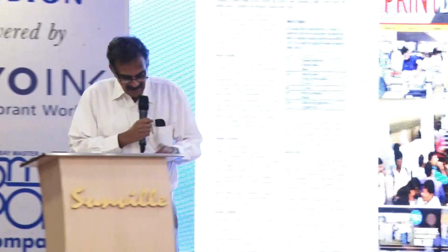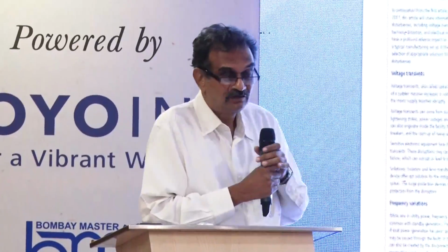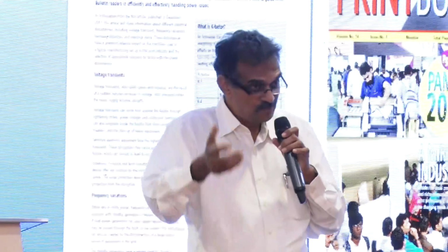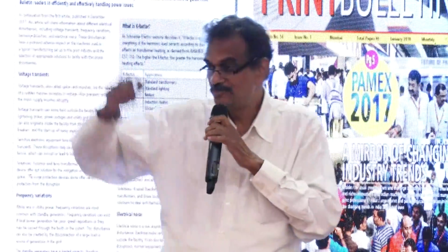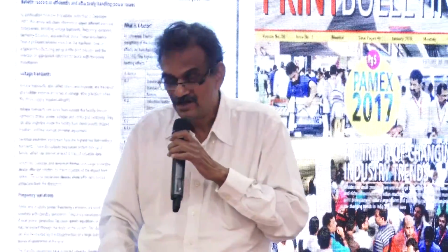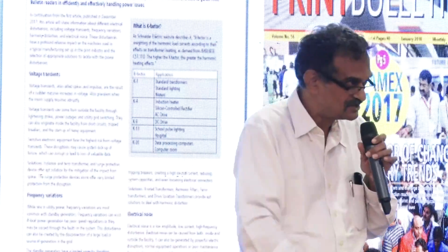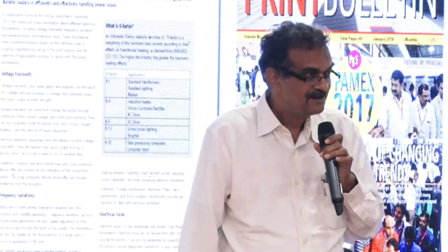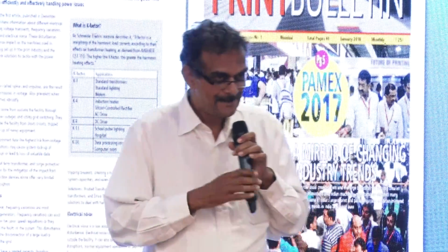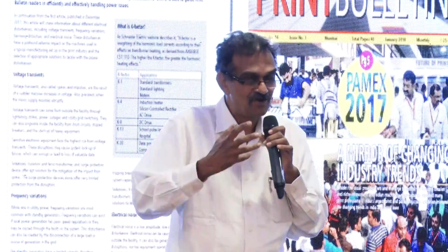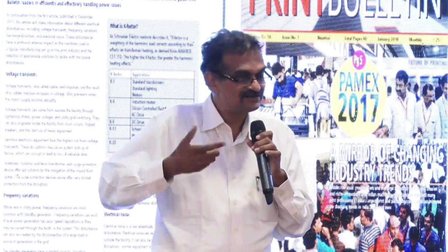So there are many issues, now we come to harmonic distortions. Those harmonic distortions are sometimes created by the UPS itself, the olden day UPSs which use thyristors, and your VFDs which use thyristors. When your thyristor goes bad, it creates such high harmonics, and those harmonics can cause burnouts because the currents are very high.